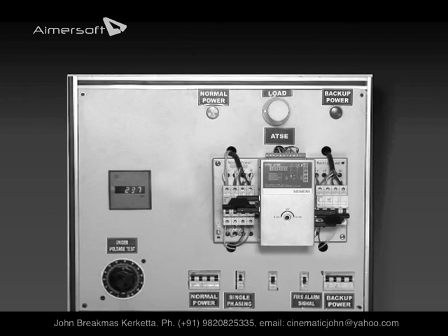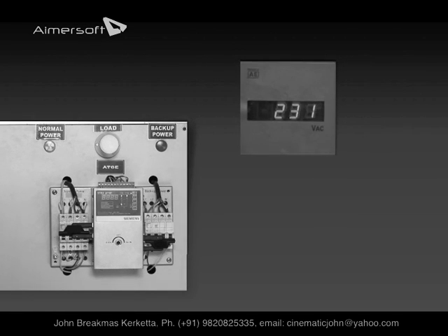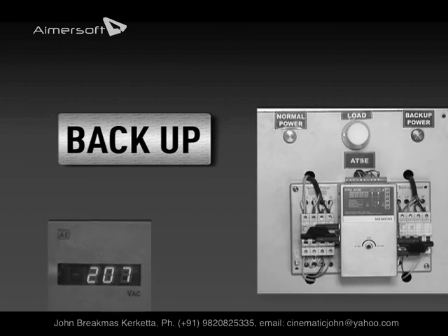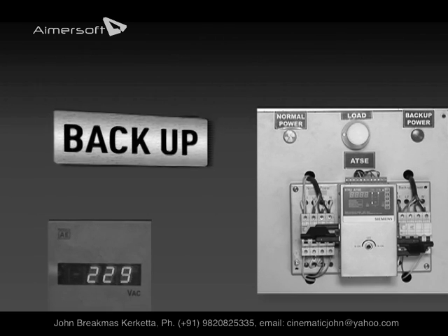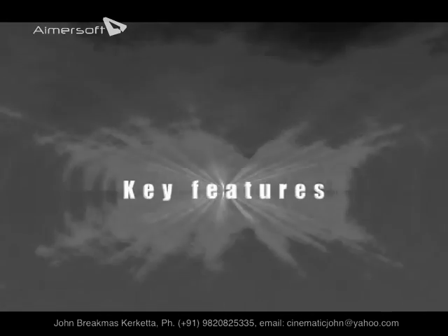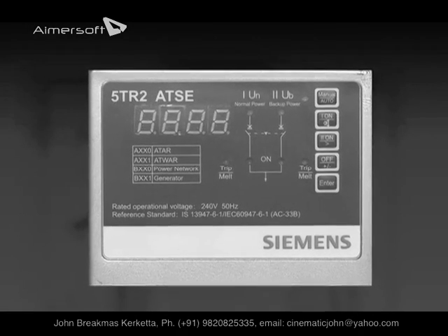This version of the ATSE has the advantage of an under voltage release. In case the supply voltage drops below 85%, down to 70%, depending on the set value of the rated voltage, the ATSE will change over to the backup power source. Once the desired voltage level is restored, the ATSE automatically switches over to the normal source.